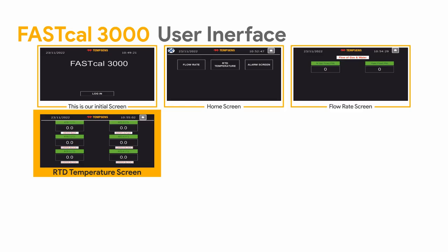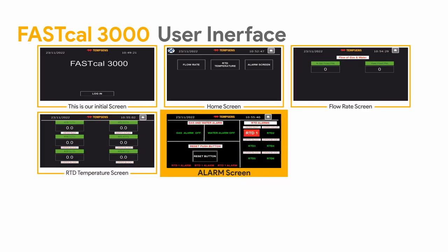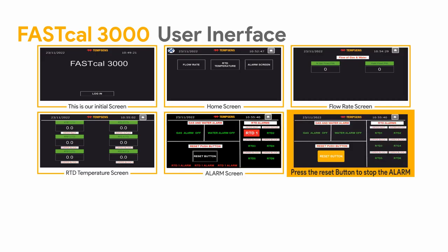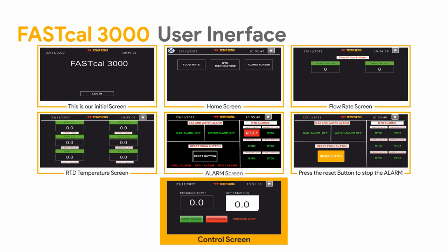In the RTD temperature section, 6 RTDs provide temperature readings. For safety, these readings are controlled by a PLC, and if any temperature limit is exceeded, the system will automatically trip, shut down, and trigger an alarm. To continue, reset the system using the reset button and return to the control screen via the home icon. Then, press start process to activate the heater and set the temperature.